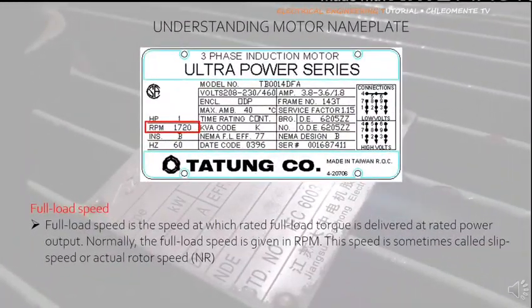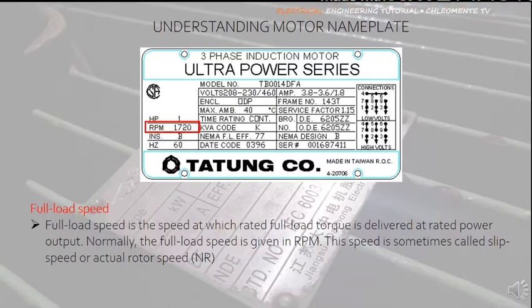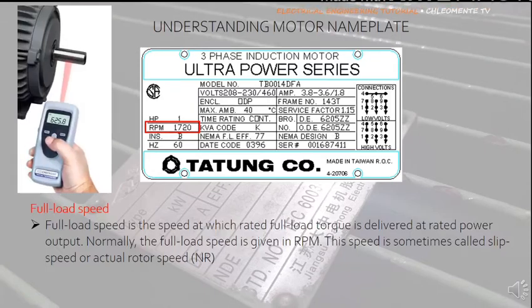RPM data tells you the full load speed of a motor when delivering its rated power output — the speed you can see on the rotor shaft when the motor is running, which is why it's called rotor speed. This data can be measured by an instrument called a tachometer and can be used to determine the number of poles the motor has. The speed formula is: Ns = 120F / P, where Ns is speed in RPM, P is the number of poles, and F is the line frequency in hertz.